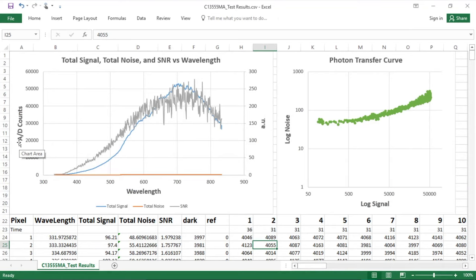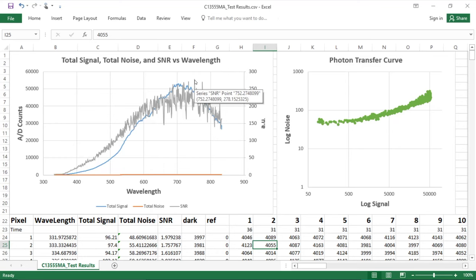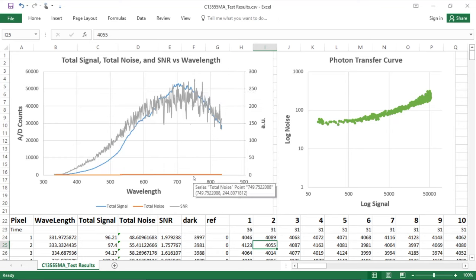So if we plot this data with total signal and total noise on one axis and signal-to-noise ratio on the other axis, we'll see that the total signal plot shows us the same figure that was displayed in the evaluation software. If we look at the SNR plot, we'll see a maximum SNR of 275 at around the 750 nm range. This plot shows the importance of knowing your wavelength range of interest as it relates to the spectrometer sensitivity and eventual SNR that is obtained.